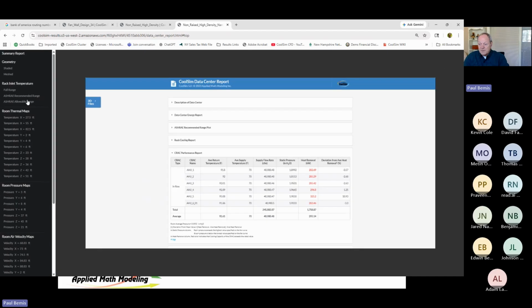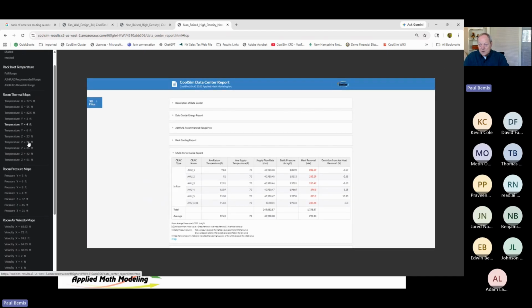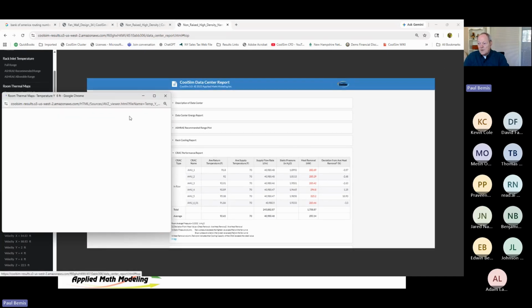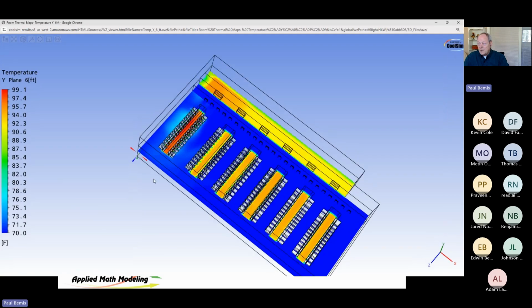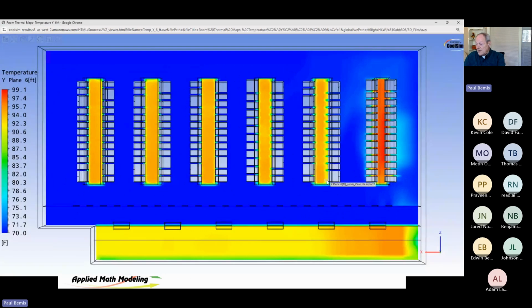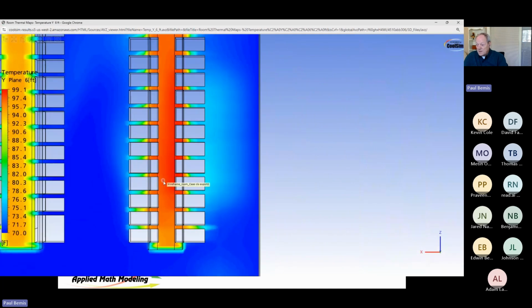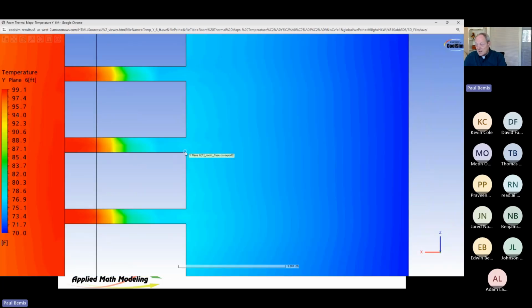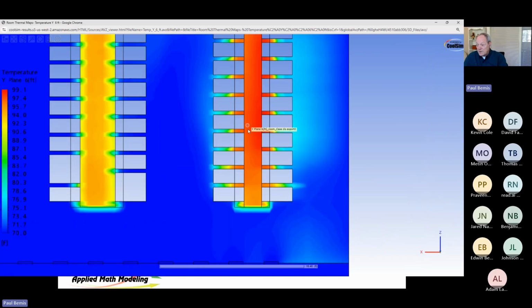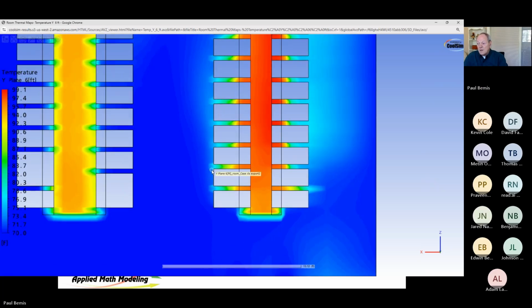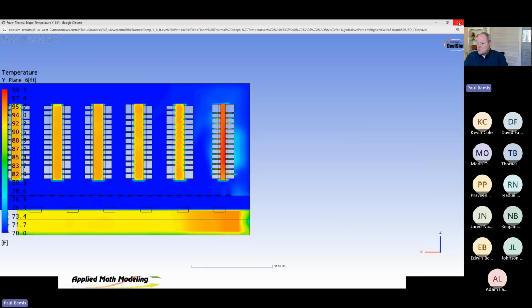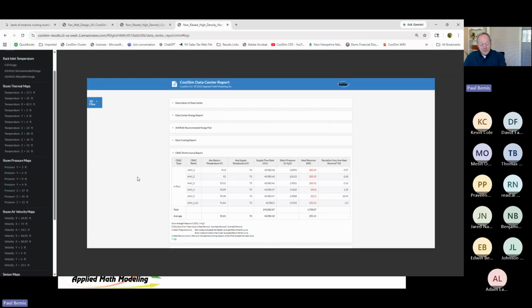And it's 9:59, but I wanted to show you leakage on this one. So let's take a look at y = 9, and you see here some problems in that narrow aisle. So I made this one narrow on purpose. You see it's leaking pretty badly. It's coming out between those rails because of no other reason. These are all set at the same load, but the aisle's narrow. So there's pressure being built up in that section, pushing it back through the rack rails.